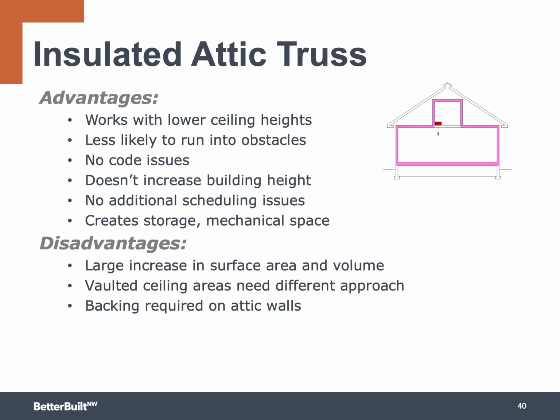Attic trusses are commonly used to capture additional living space under a steeply pitched roof. The same approach can be used to create a utility room that's fully insulated and sealed. This room can house the air handler as well as the return and supply plenums. It may also be used for major duct runs. One drawback to this strategy is that the side walls, sometimes called the knee walls, must be fully insulated and the backside covered with rigid material. Air barrier continuity must be maintained by blocking and sealing the bottom plate of the side walls to the ceiling gypsum board below. Also, this approach does increase the conditioned volume of the house.